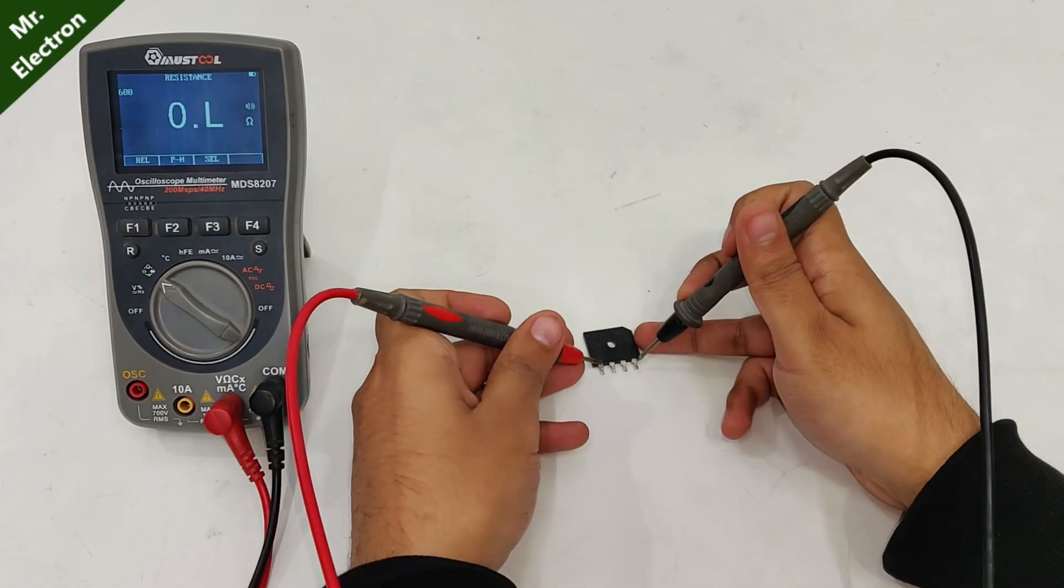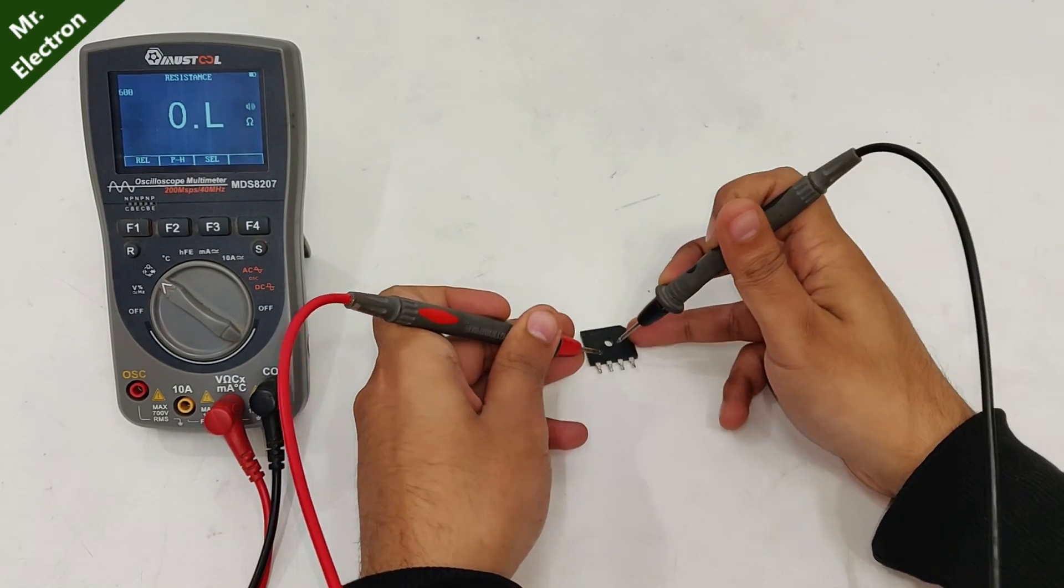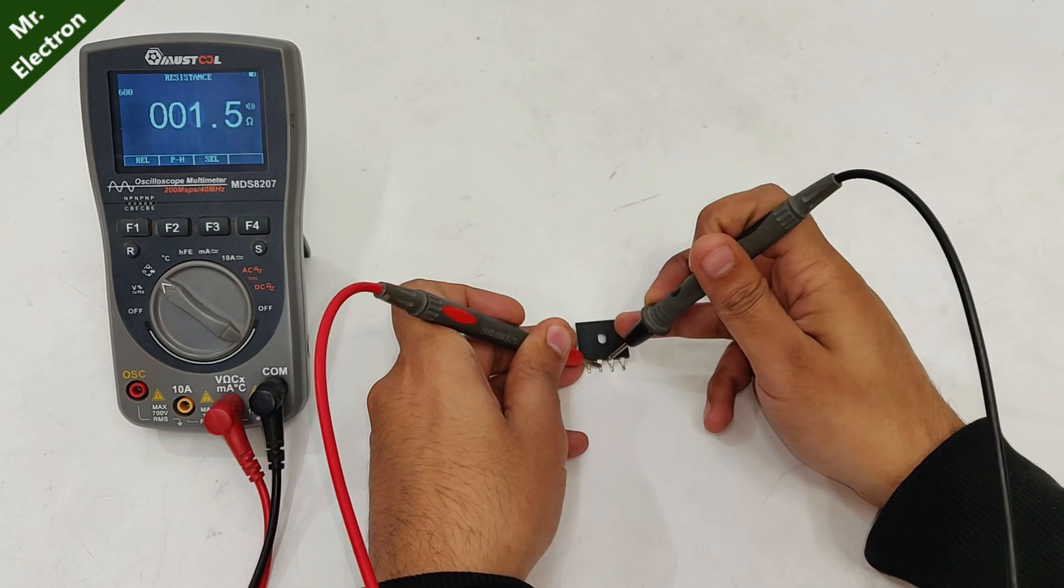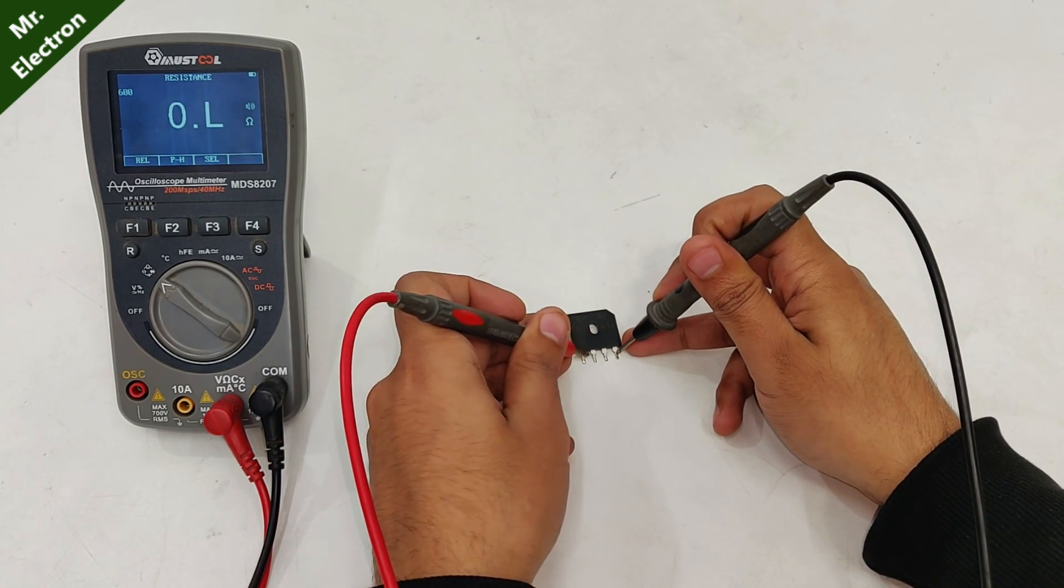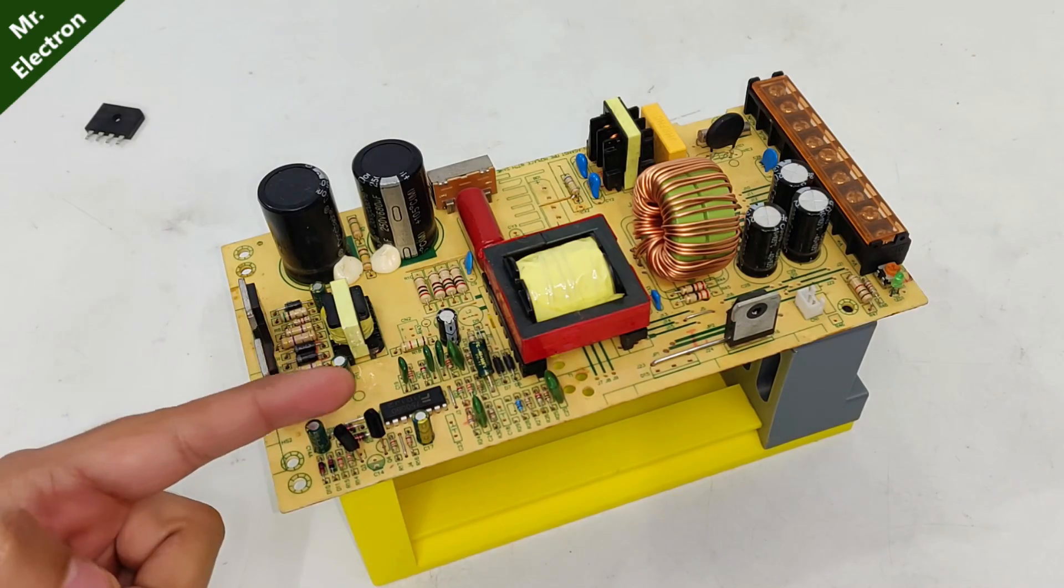So checking the rectifier once again. It's fine. It's fine. It is fine, not short, which means the problem might be on the DC side.